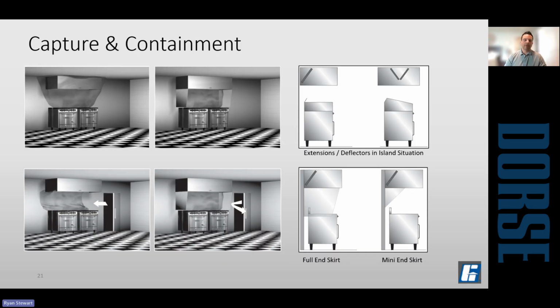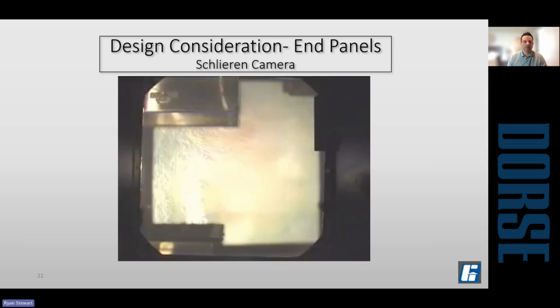So, capture and containment panels. With a hood with 6-inch overhang, as that convective heat plume rises, it's going to expand. And you can see from the illustration there's a good chance that some of that convective heat is not going to be captured by the hood. So you can add stainless steel containment panels to help force that up into the hood. They can also help alleviate drafts from doorways, walkways, and things that are happening inside the kitchen.